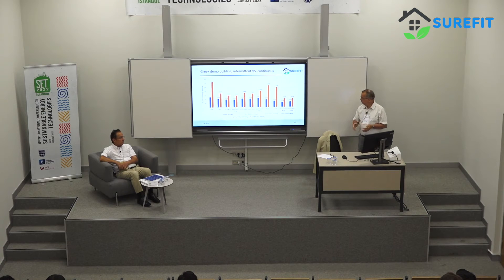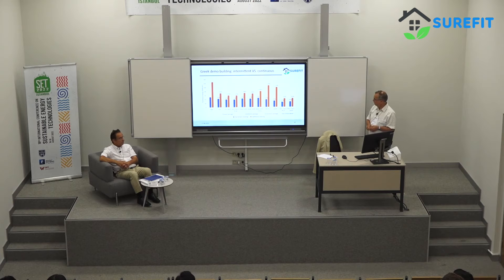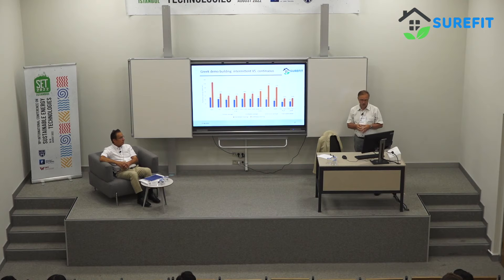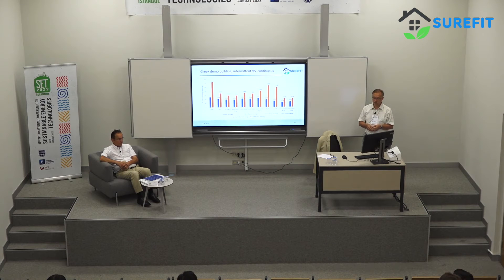With intermittent heating, energy generation measures have much higher potential. Looking at savings for energy consumption and CO2 emissions — the target is 60% — for Greek buildings with intermittent heating we reach about 50% reduction. But if buildings are used with continuous heating, the efficiency is much higher: over 60%, reaching 65–66%.